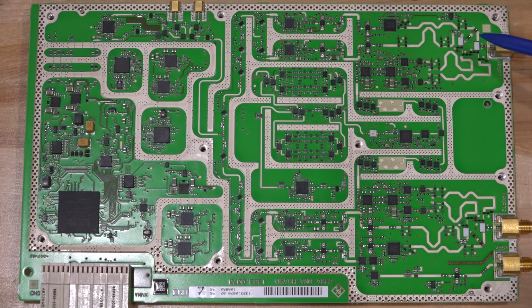Why not? So in the very front of port 1 and port 2, we seem to have some couplers, and these appear to be resistive couplers, and I've talked about these types of couplers in network analyzers before. By doing a vector measurement across a bridge in the appropriate places, when you have a stimulus signal, you can actually figure out the exact impedance connected to each of these ports. And of course, from that, you can extract the network analyzer S-parameters after doing some calibration. So I think that's what's going on over here.